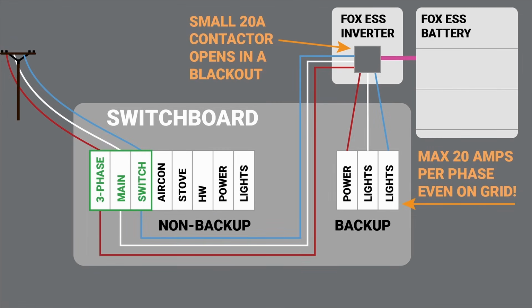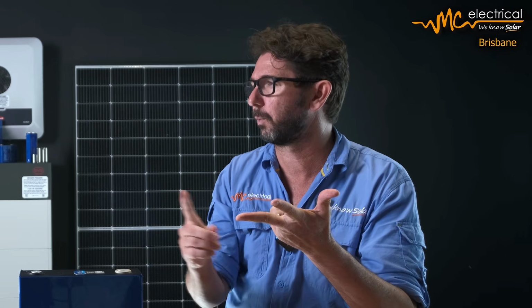It turns out that we had drawn more than 20 amps through one of his circuits, and the inverter trips off. So this is not in a blackout situation, but even when you're on grid, there's a contactor within the inverter that can't take more than 20 amps on grid. So what it really means, if you're backing up on one of these larger 15 kilowatt inverters, all you can do is run one power circuit on one phase, one power circuit on another phase, and maybe one light circuit on another phase - I'd say two, but I might be a bit more daring than you are.